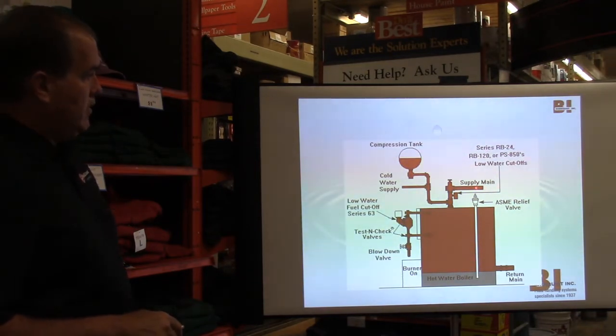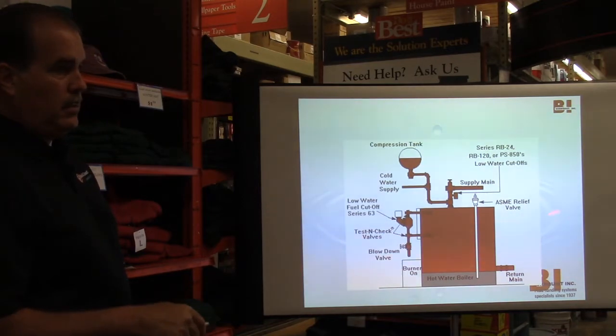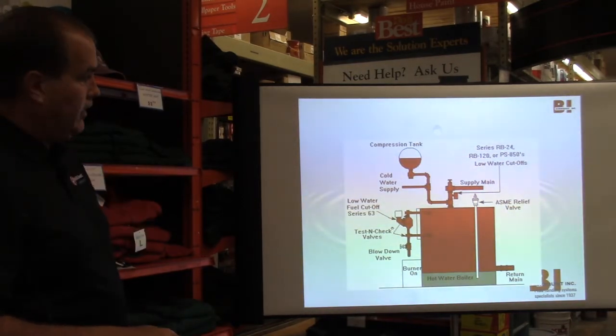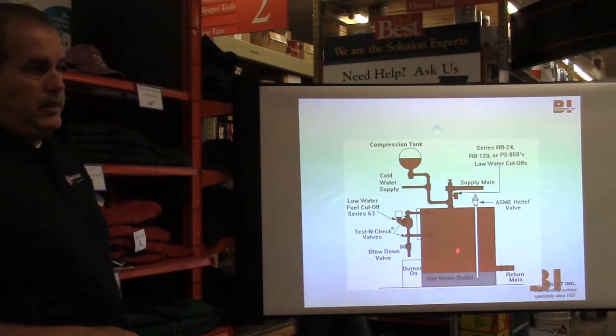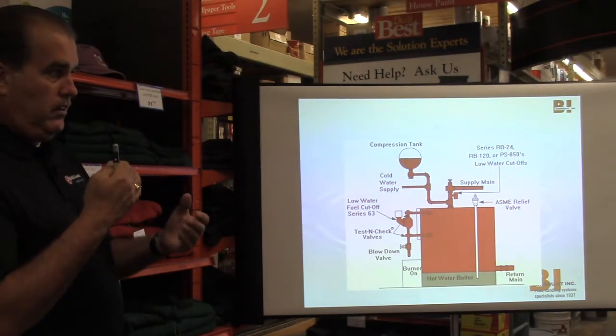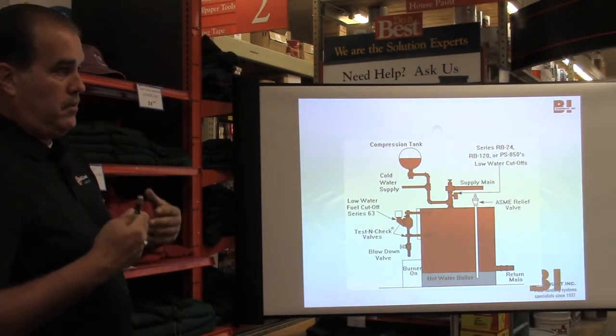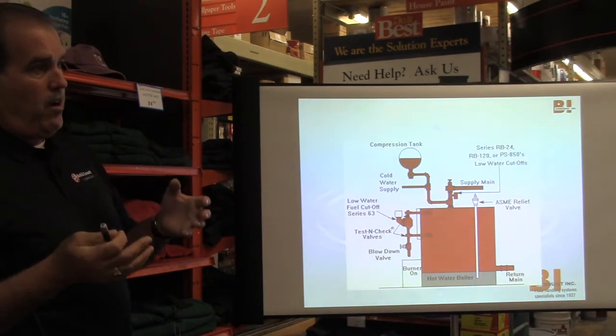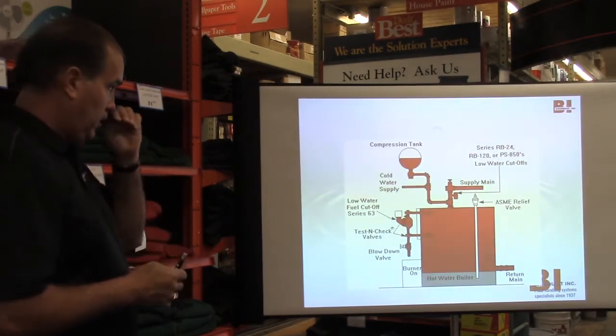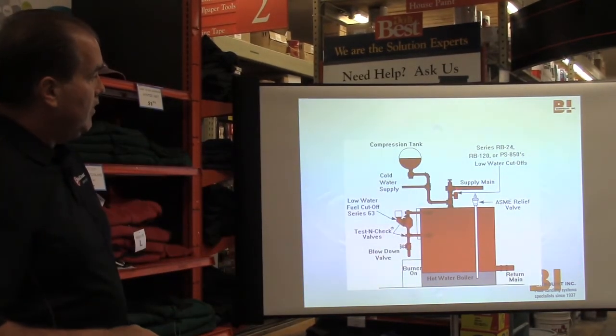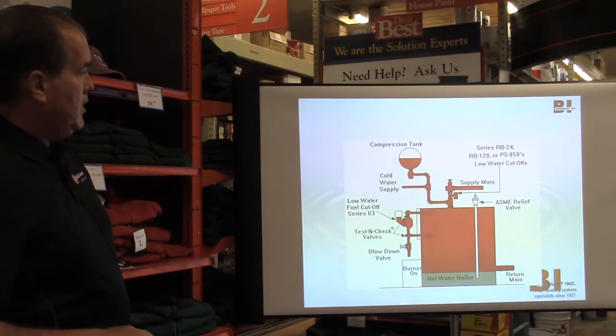Imagine this pipe goes out to your building, does all the things at the radiators, heating everything, and then comes back cooler, because when it goes through a radiator, there's a temperature drop because you're moving the hot water potential into the room to heat the air. So that's your typical arrangement.